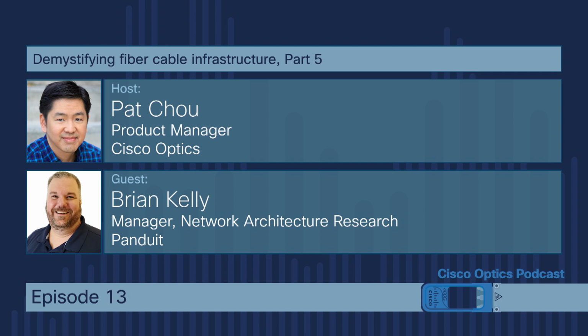The duct goes from the back of the switch to the front of the cabinet, so cold air reaches the backside of the switch without getting muddled with hot air coming in from the back of the cabinet. This actually makes a huge difference in switch performance, because depending on your switch location—usually at the top of the rack—heat rises, and depending on how densely populated your server cabinet is, the heat could be intense and you'd be pulling in a lot of hot air. Whereas with this duct to the front of the cabinet, it pulls in the 67-70 degree air that hasn't mixed with the hotter air yet, and it won't mix because the ducts are designed to ensure enough air gets to the switch itself.